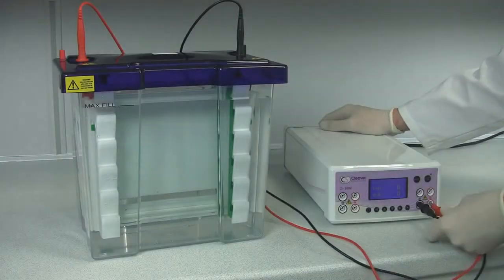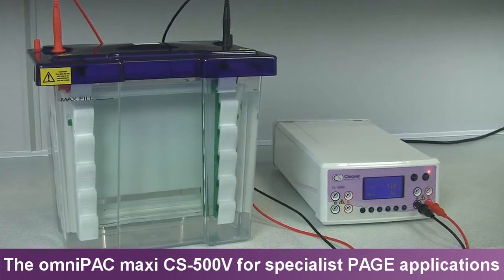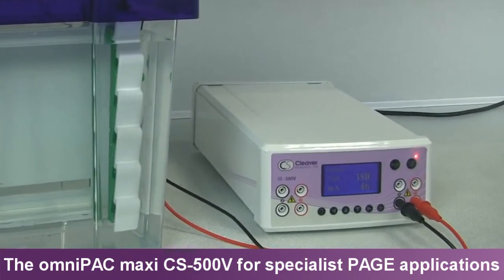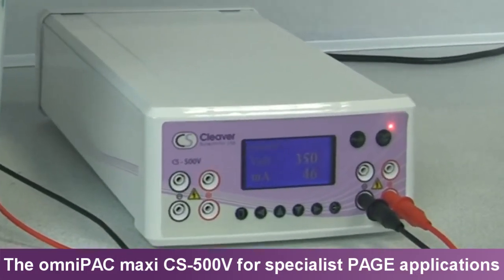With a maximum 500V, 800mA and 300W voltage, current and power output, the omniPAC CS-500V is an excellent general purpose power supply that fits the broadest range of electrophoresis applications. It can run as many as 4 units under a constant or programmable setting.